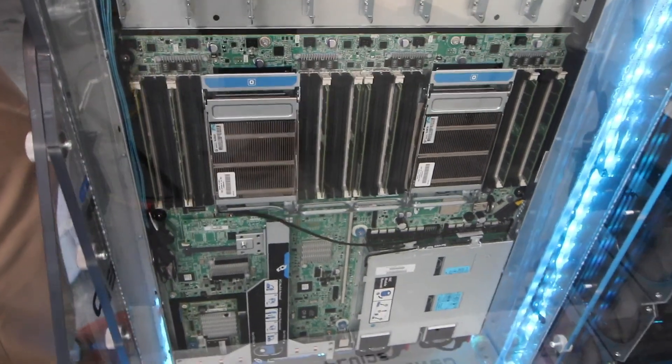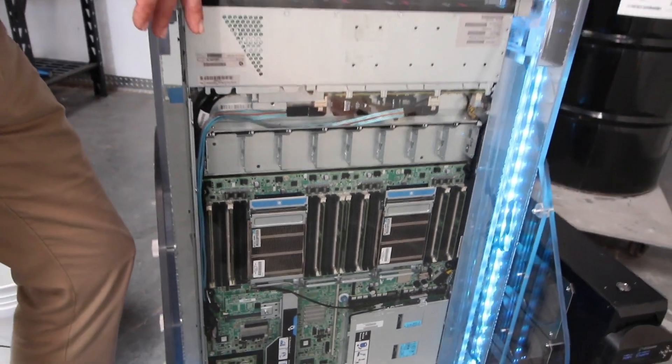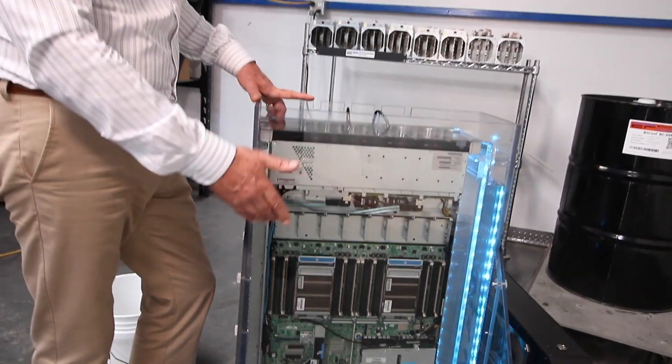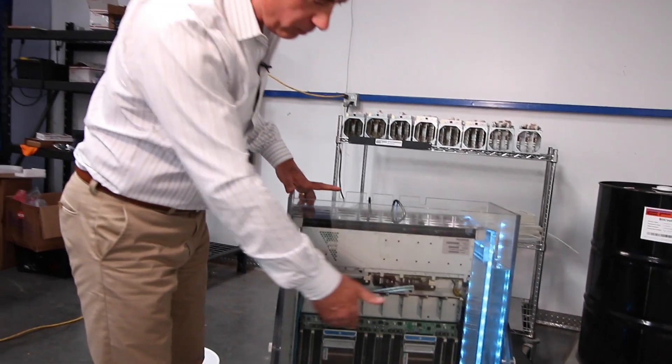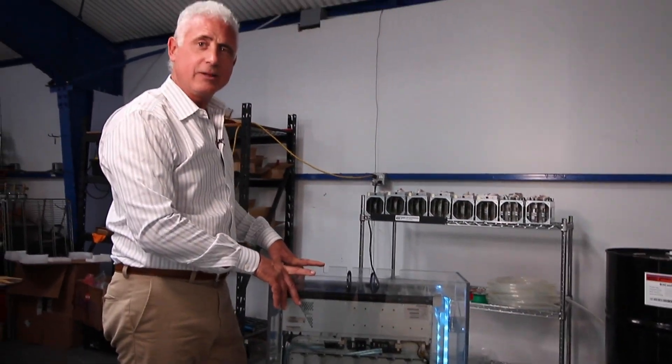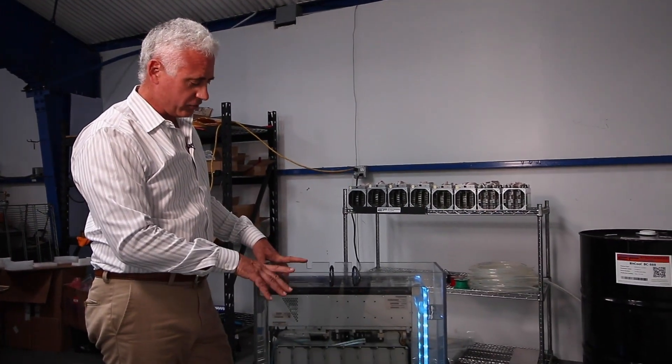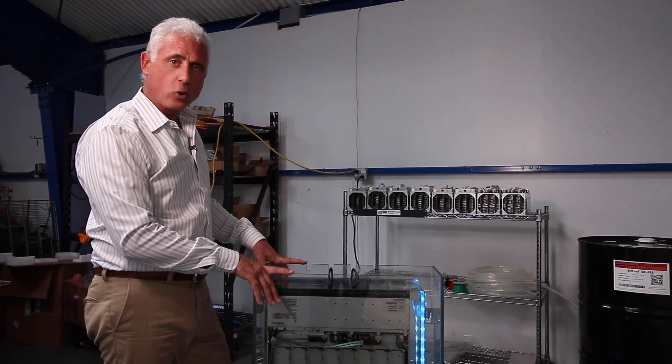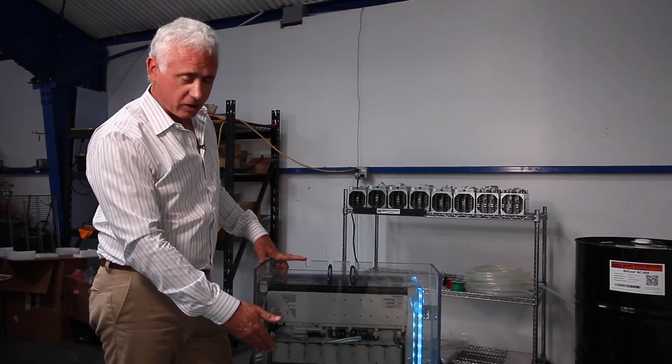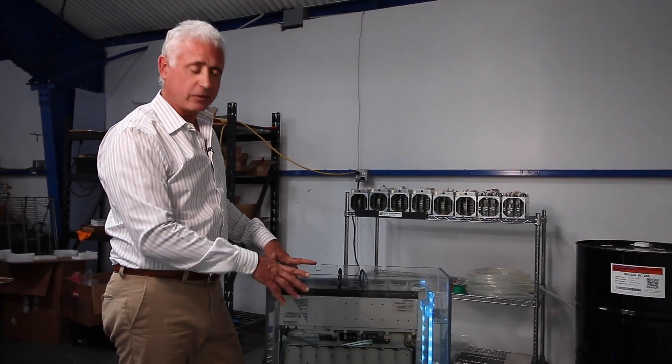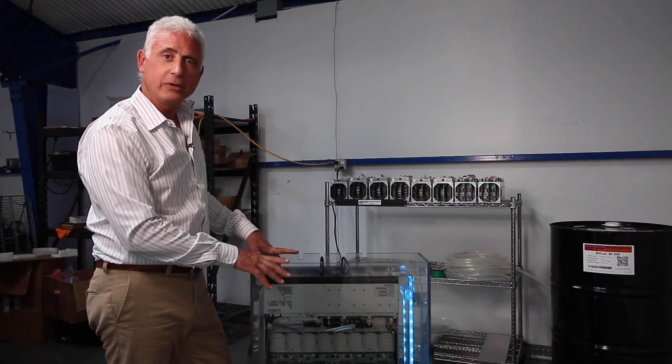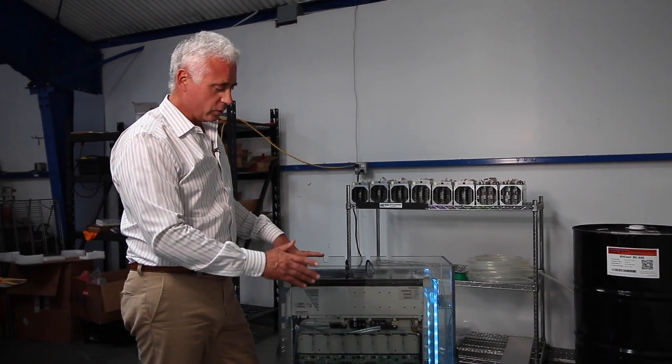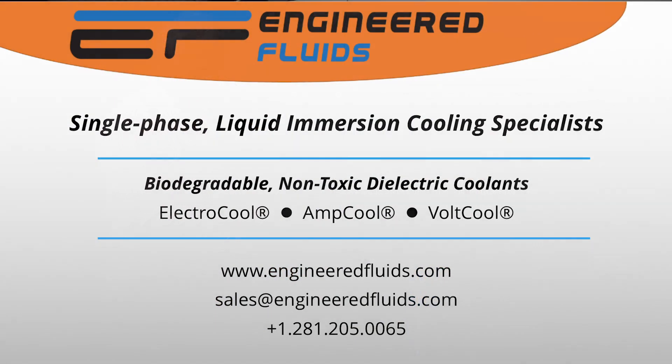The final thing that we always do is make sure that we've deactivated any alarms that will come out of the fans being removed. Because we actually don't need any of the fans as we mentioned earlier in these devices, but normally these servers will go into alarm when the fans are not present because the device believes that it's going to overheat. So what you do is we go into the BIOS and we disable those fan alarms.